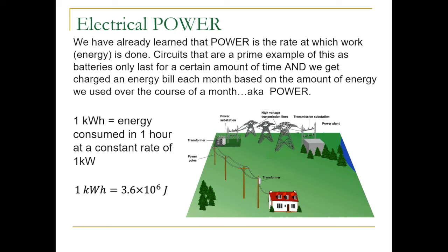And the answer came down to Ohm's law, an understanding that if we have an exceptionally high voltage traveling through a line at exceptionally low current, the result is going to be far less power loss as it moves from the power plant to the power substation and inevitably to our homes.